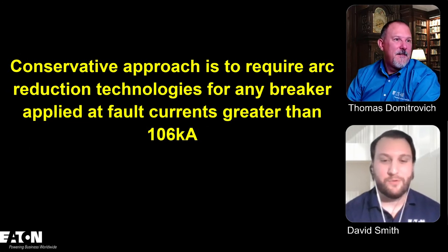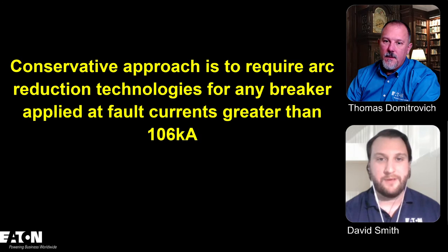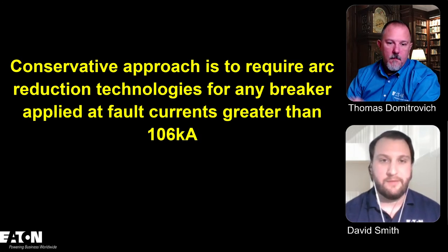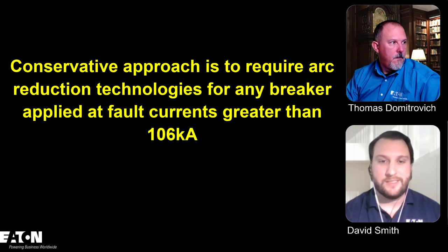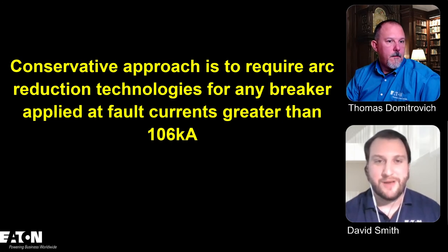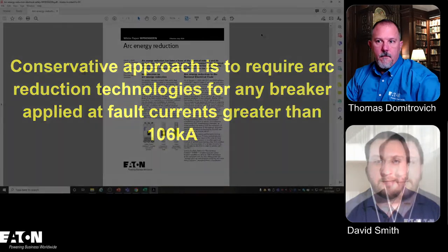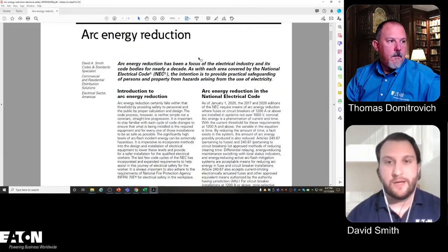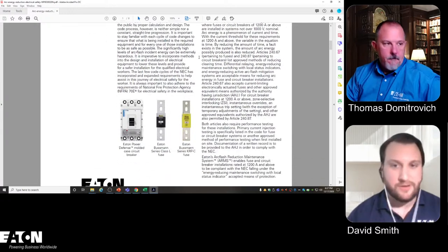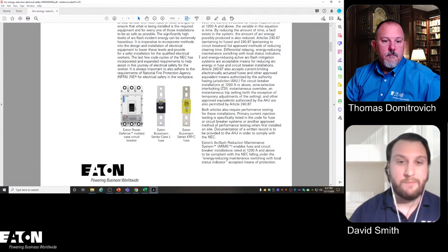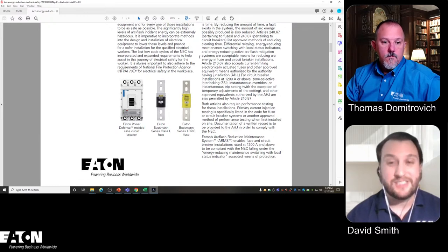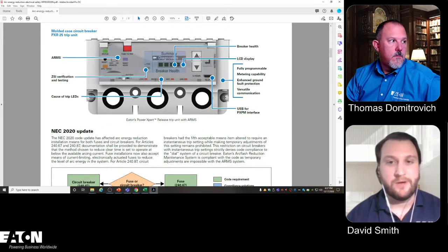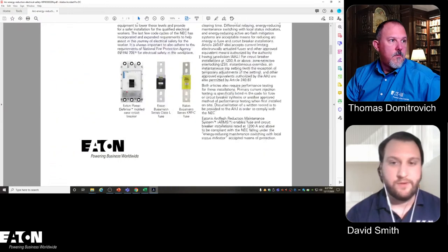That's true. One thing I did want to mention real quick, just to make sure we're not going to get off topic. Of that particular white paper that I wrote, I couldn't remember what made the cut and what didn't. As you know, some things do not make the cut. But what did make the cut was, under my 240.67 parts, I have calculations for examples of systems that do and don't need this particular stuff. I know we're talking about 240.87, and I keep on mentioning 240.67. The reason I do that is because I mentioned both of these articles in the white paper, and they're basically sister articles. They're talking about the same thing whenever it comes to arc energy reduction. One's for fuses and one's for circuit breakers.